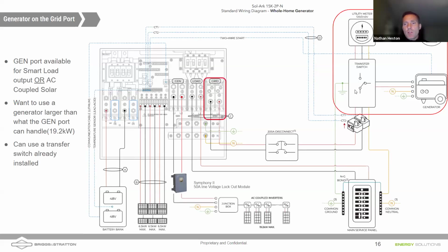So I'm showing you, if you've got a Briggs & Stratton transfer switch, one of the things you're going to want to do is make sure that AC coupled solar won't backfeed the generator. And you can do that with a line voltage lockout module. So typically those homes that already have AC coupled solar on the roof, we already know, AC coupled solar doesn't give you any backup in an outage. So adding a battery-based system like a Sol-Ark, you can bring in that AC coupled solar. Typically you're looking at 20 amps or 40 amps of AC coupled solar. But you don't want that solar running if the generator's running. And because that generator's coming through the grid port, we recommend installing a lockout module like this Symphony II.